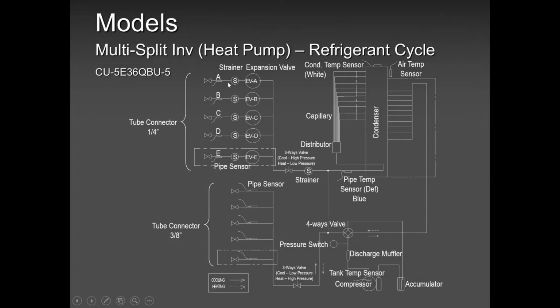These are your sensors. Okay, on each and every pipe we have a sensor. Okay, we have a sensor on the liquid, we have a sensor on the suction, and then we have the electronic expansion valve. So when you power the unit, you hear the A, B, C, D, and E clicking. They click, and they make sure they work fine. If you don't hear the clicks, definitely you have a power problem. Okay? And if the system has been running fine and all of a sudden you have a problem, the customer is getting some blinks, go outside, you shut the power off, power back on. If you don't hear the clicks, definitely the problem is outside.